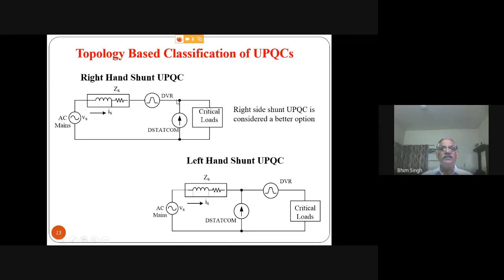But in this case, the current rating of the DVR will reduce, because you are now putting sinusoidal and balanced current into the DVR, in phase with the grid. So a minimum current will go through this without distortion. So the current rating of the DVR will reduce here compared to there. That's the reason this right-hand shunt topology is preferred in the case of UPQC compared to this. And we prove that by many numericals and also analytically in our book.